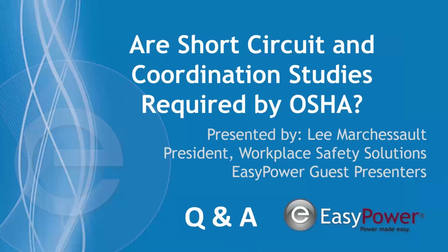Okay, so this is from Joseph. What if the voltage rating of the switchgear is lower, but the breaker is rated properly? So, I understand that. You have an example like a 208 rated panel that's installed in a 480 volt system with 480 volt breakers. As long as the breakers are rated for the available fault current, they aren't going to fail themselves, but the panel may fail, because the insulation between each phase is going to be less on a 208 volt panel than it would be on a 480 volt panel. Generally, just energizing it doesn't cause it to blow up. But you'll want to treat it just like an overduty panel, and replace it as soon as you can, because the insulation between phases and phase to ground, well, mostly phase to phase, is going to be different. Well, phase to ground too.